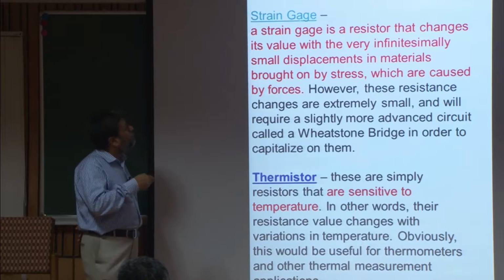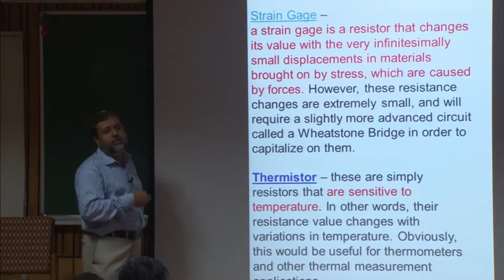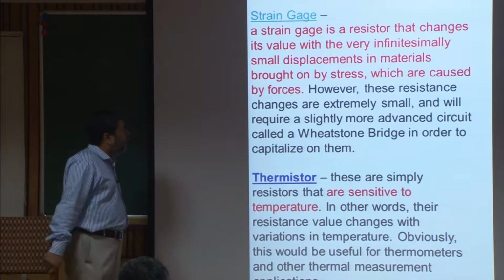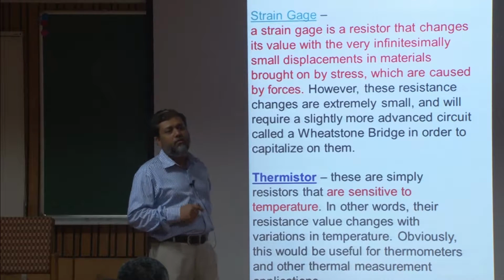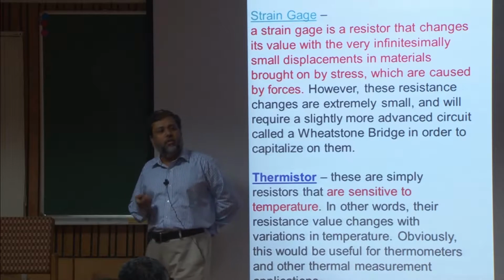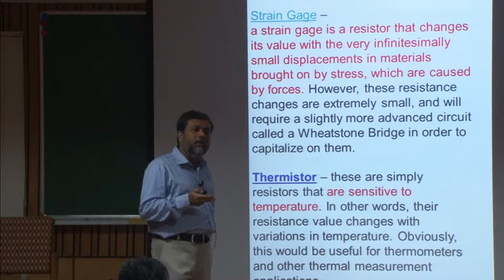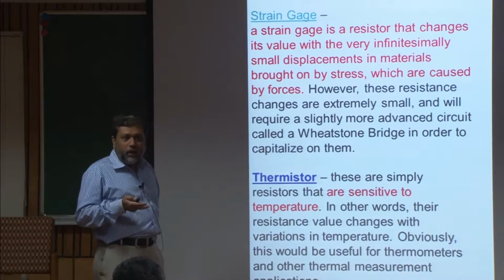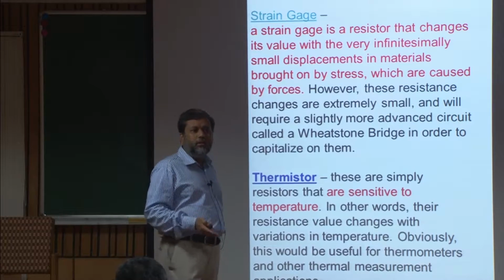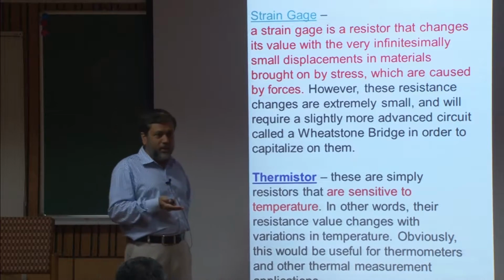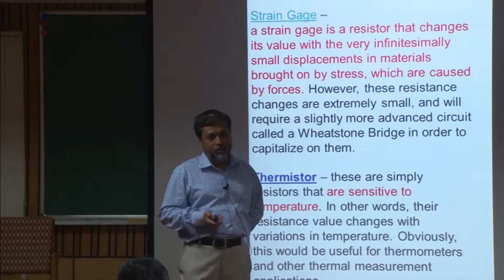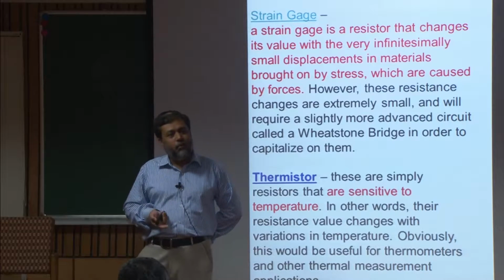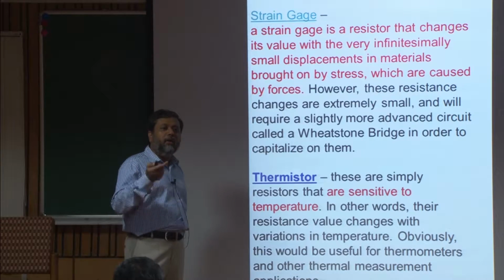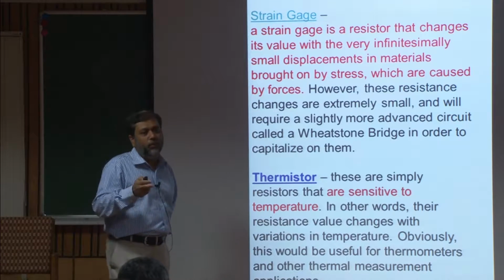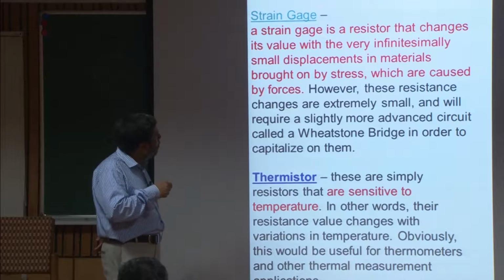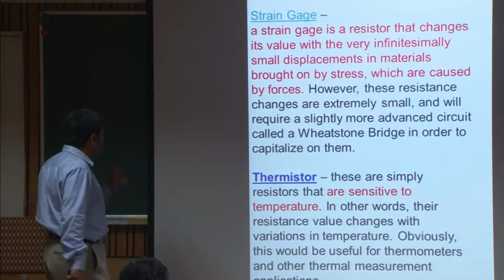This kind of resistance change based system is an active system - it needs a power supply. There's a passive version called piezo resistors, where the piezoelectric crystal generates voltage, and depending on the stress, it changes its resistance, which affects the voltage generation. So you can directly use the same crystal for the change of pressure creating a change of resistance, and that creating a change of voltage generation - the active-passive counterpart of the strain gauge device.